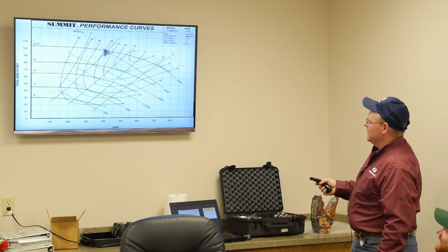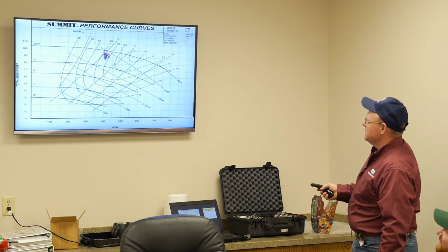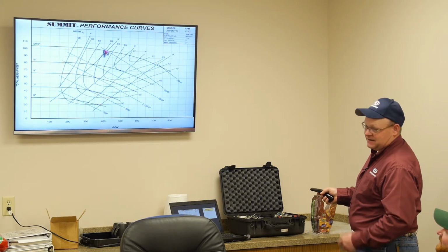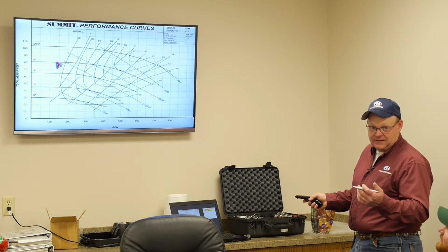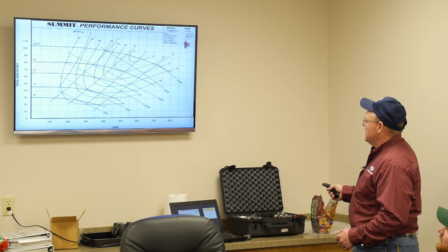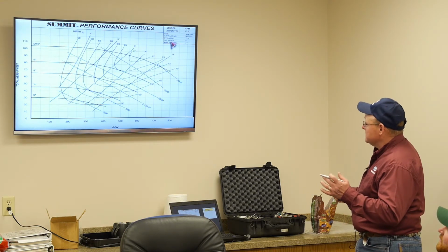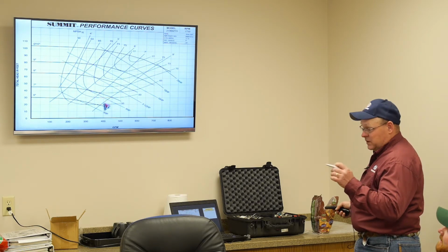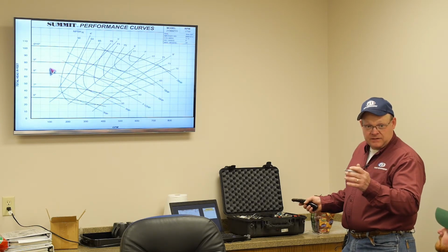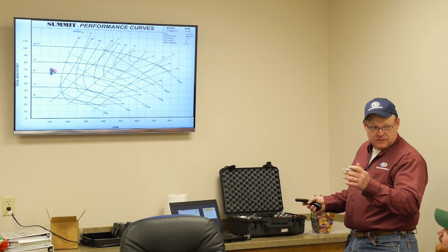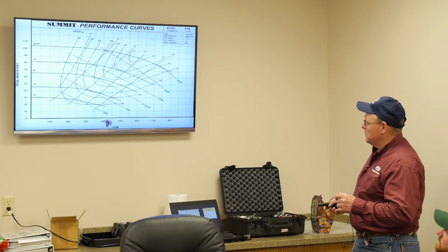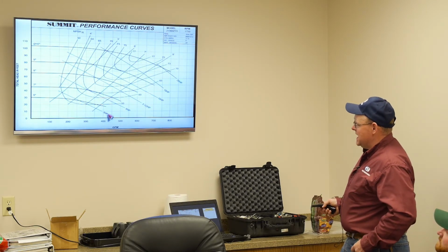Let's take a point on the curve, just right there. 400 gallons a minute, 100 feet of head. That's easy. That's 43.4 pounds, right? So if we take the same pump, but we're going to put the 3,500 RPM motor on it. Everybody with me? So we're going to go twice the flow. So now we have 800 gallons a minute.